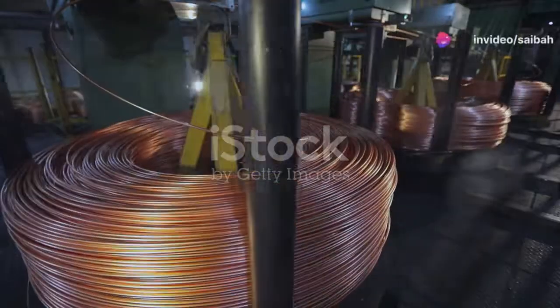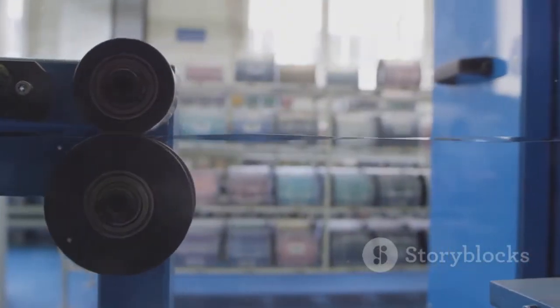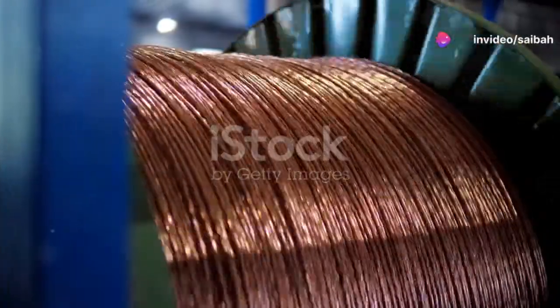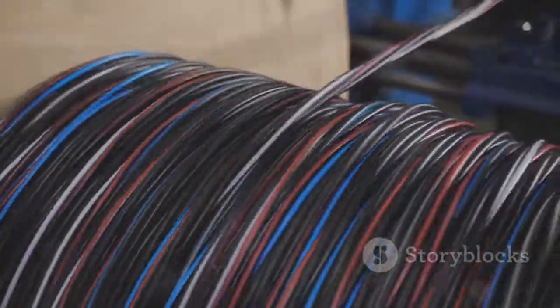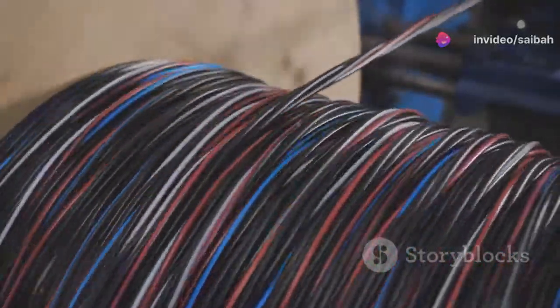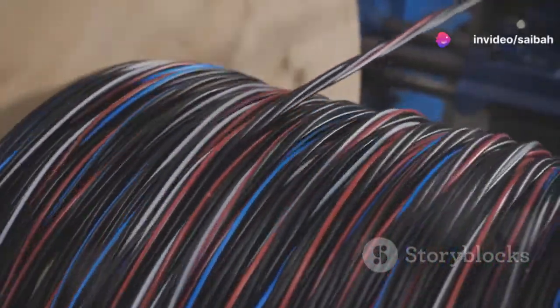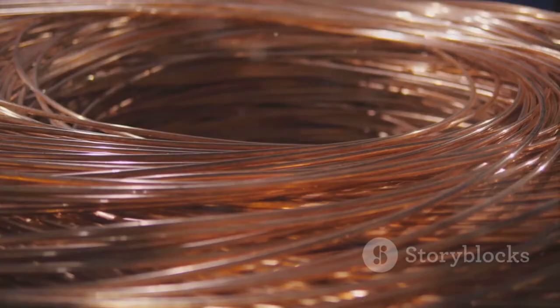They are the unsung heroes, ensuring both the safety of the user and the efficiency of the conductors. Electronic cable shields minimize the effects of external electromagnetic signals and reduce radiated signals from the cable, while power cable shields protect the user from shock hazards and increase cable reliability. Diving deeper, we explored the conductor and outer shields in power cables. The conductor shield provides a smooth, continuous, and void-free interface between the conductor and insulation, preventing harmful partial discharges. The outer shield plays a similar role, but on the exterior of the insulation. And let's not forget the copper tape, often used in power cable shields, which forms a crucial part of the metal polymer shielding system. So, the next time you look at an electrical cable, remember the intricate shield system working tirelessly to keep our electrical system safe and efficient.